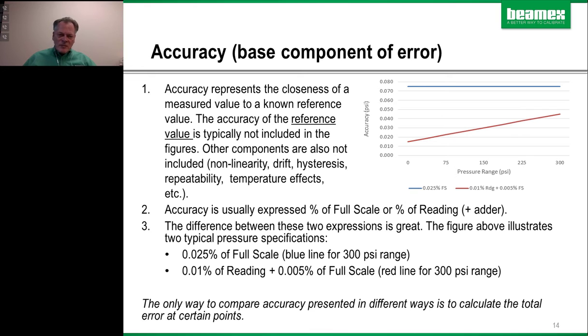But notice these things that are missing in accuracy. There are other components of error. So accuracy is just one component. But how linear is the instrument? How much does it drift over 6 months, over a year? Is there hysteresis? Does it measure differently when the signal's going up versus when it's going down? How repeatable is that measurement as you change? How about temperature effects? How's that instrument perform on a cold day versus a blazing hot day? Things like that.